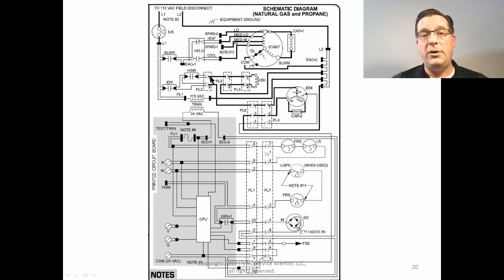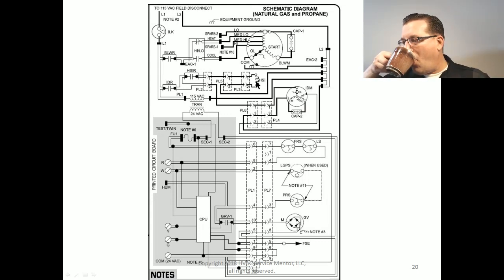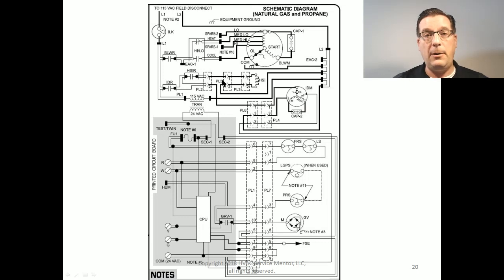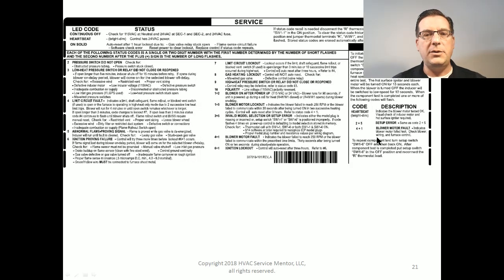And when it does, 120 volts is going to leave on PL3, or I'm sorry, PL2, into PL5, out to PL3. Those are plug numbers, the Molex plugs that come apart. There's a couple of them on this one. Could it be that one of these wires is broken? You betcha. So that's what's involved in the troubleshooting: you have to understand exactly what this board is trying to do, identify how it's doing that, and identify whether or not it is doing that. And that takes a minute or two, right? It's not always immediately obvious, but that's what it takes. It takes a little bit of time. It requires you to take a look at the sequence of operations and identify what's going on.